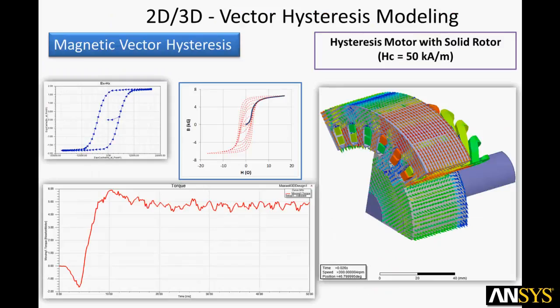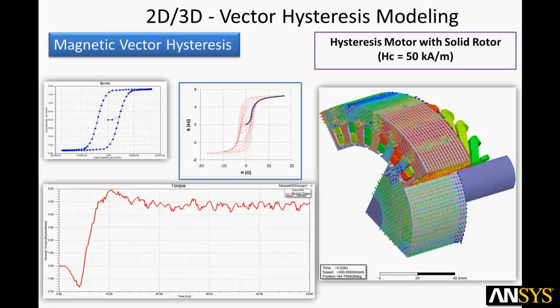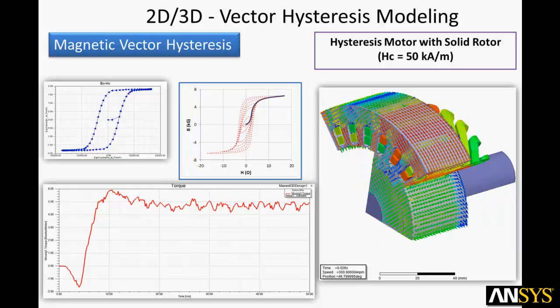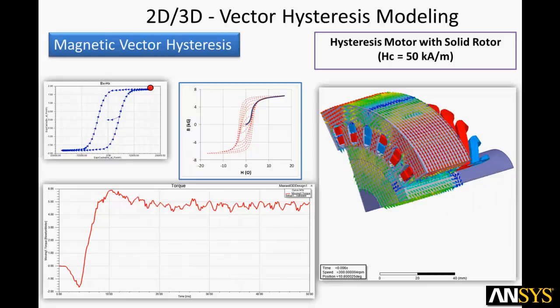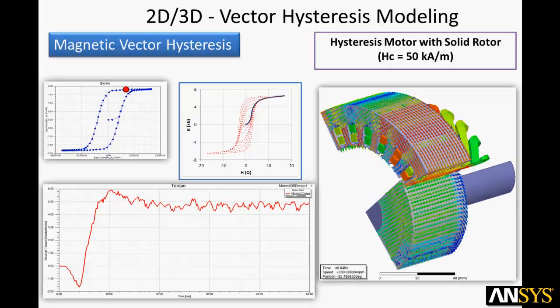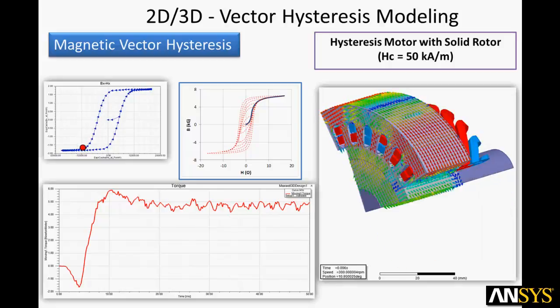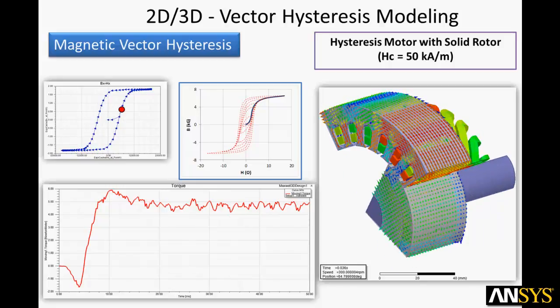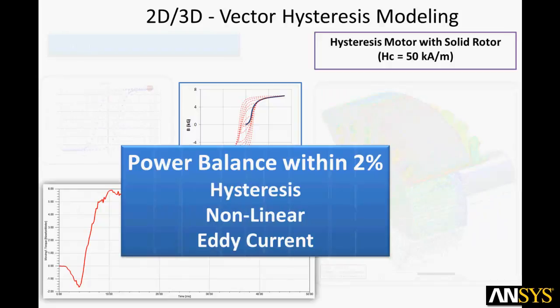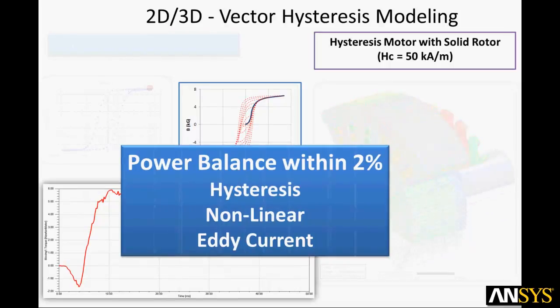Here you see an example that requires the most advanced magnetics modeling. This hysteresis motor has a solid rotor with a thin layer of ferromagnetic material that provides dynamic magnetic pole creation. This can be modeled only if the ferromagnetic material demonstrates hysteresis. Accurate prediction of motor efficiency also requires nonlinear modeling and eddy effects. A measure of accuracy is the power balance between electrical input power and the mechanical output power, including various losses.